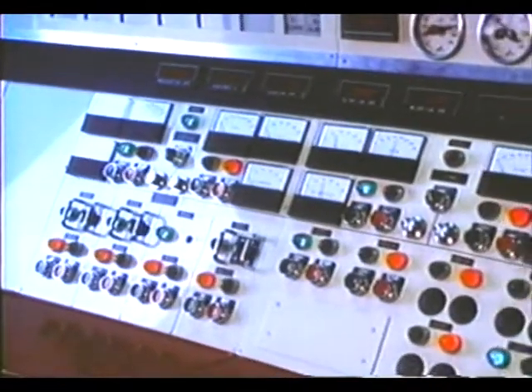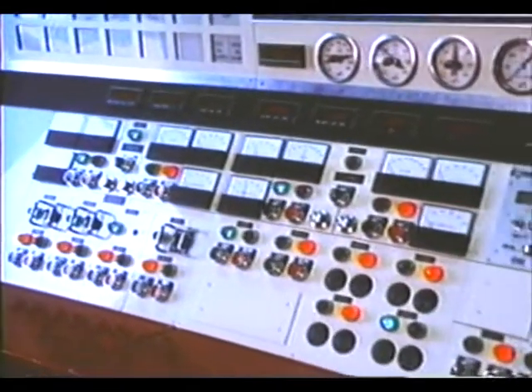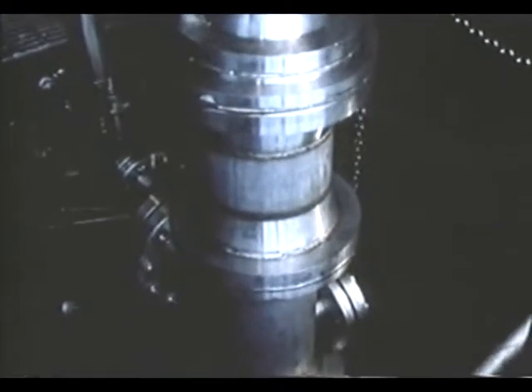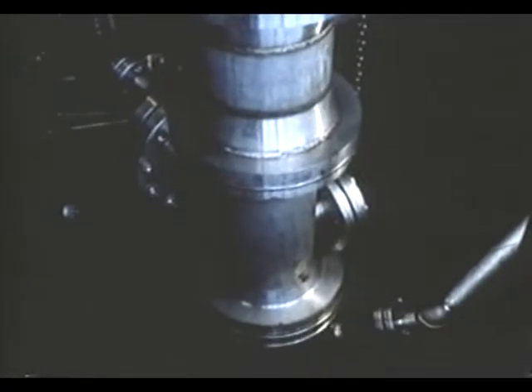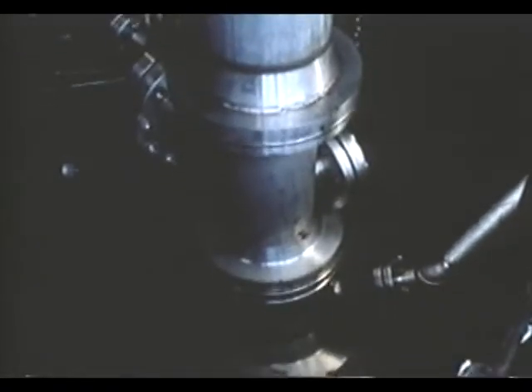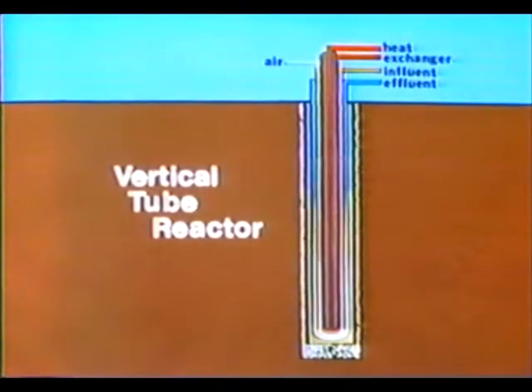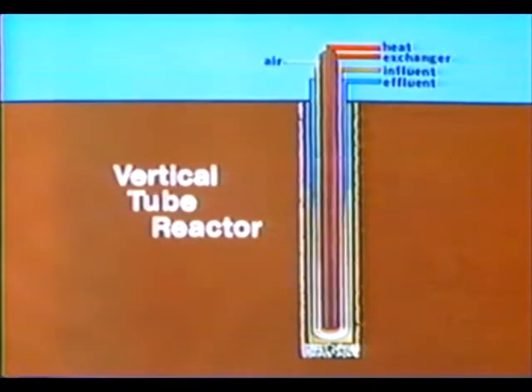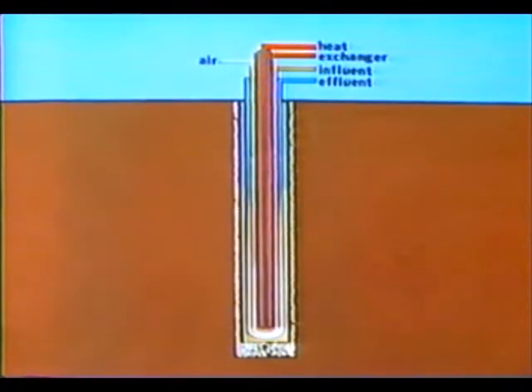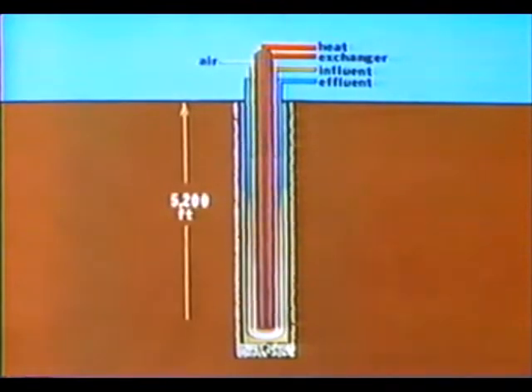Wet oxidation principles have long been recognized, but until now, the operating costs and technical problems associated with high temperature, high pressure, above-ground equipment greatly offset the potential benefits. The unique patented design of the vertical tube reactor utilizes the natural laws of thermodynamics within a simple annular heat exchanger enclosed in a conventionally drilled, encased vertical well, 5,200 feet deep.